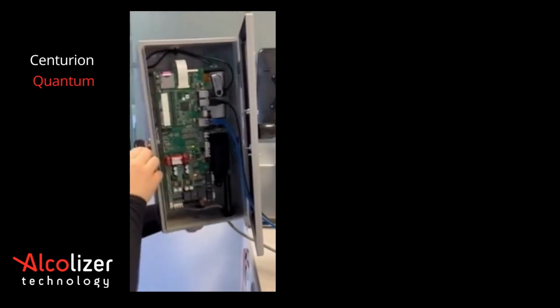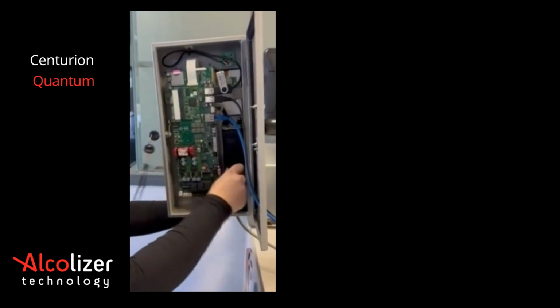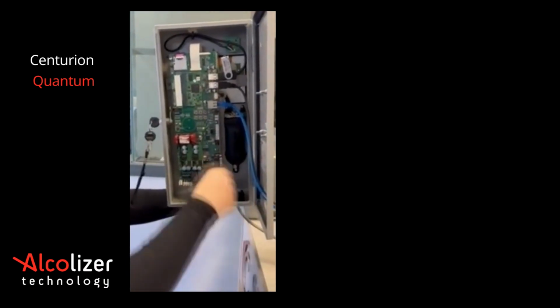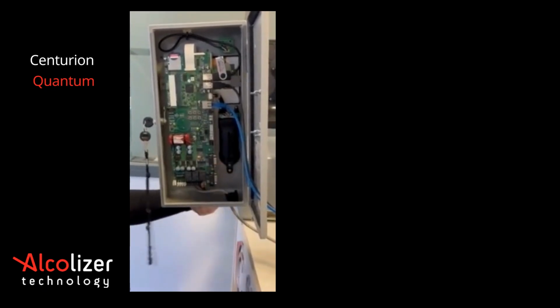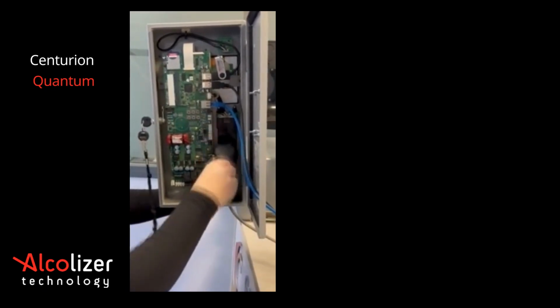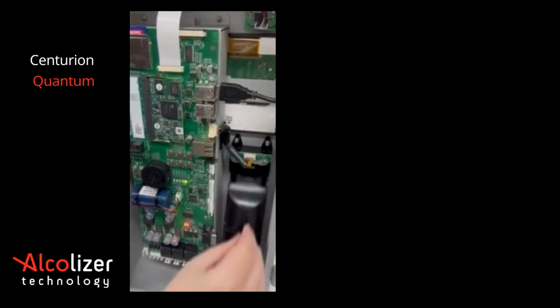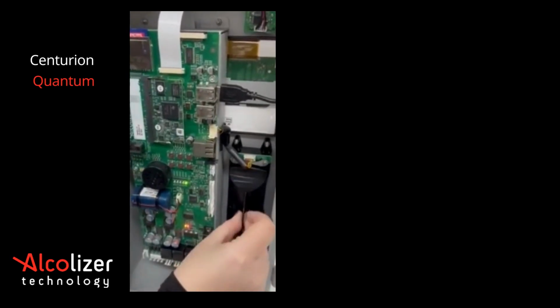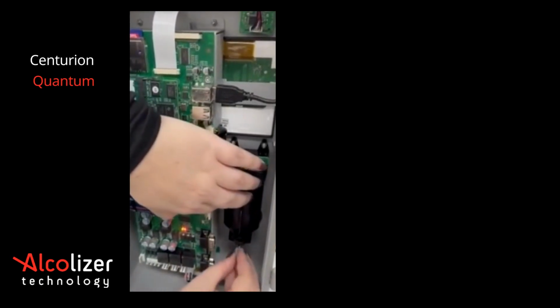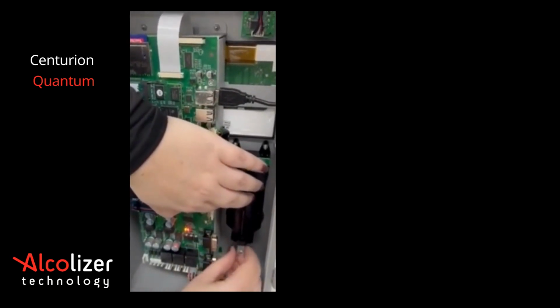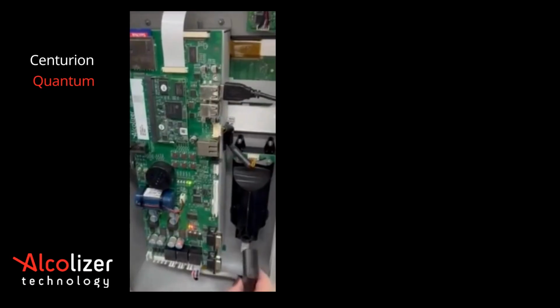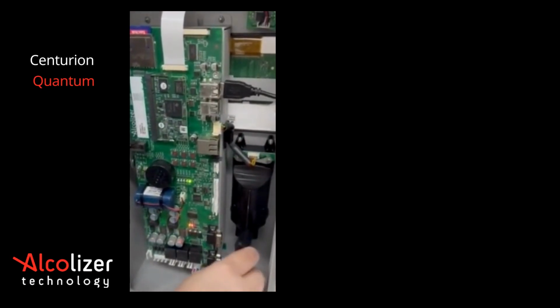For Centurion Quantum, begin by opening the device and pressing the off button. Remove the drain tube and unscrew the aluminium thumb nut carefully. Remove the expired module. Insert the new calibrated module and tighten the aluminium thumb nut to secure. Attach the new drain tube. Press the off button again to restart the device and close the unit.